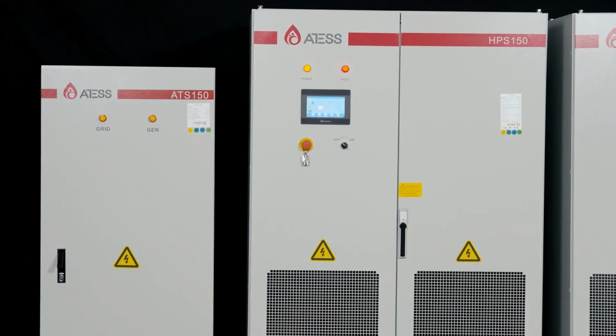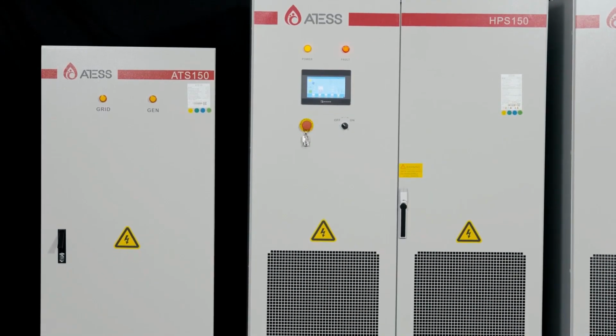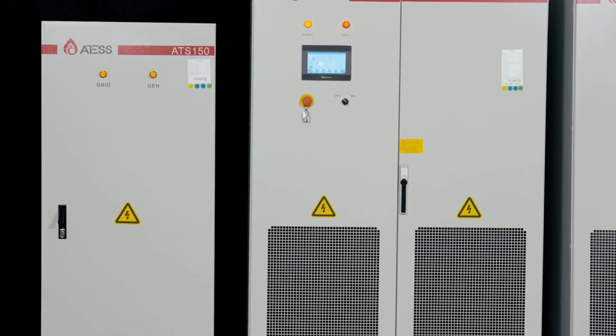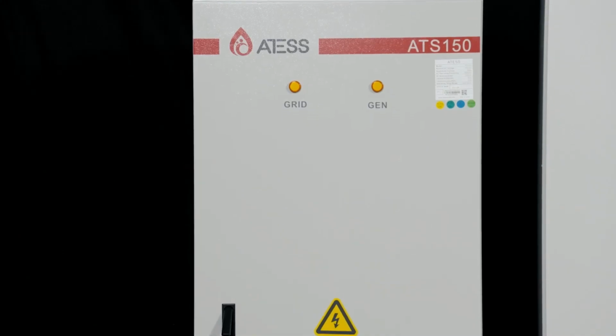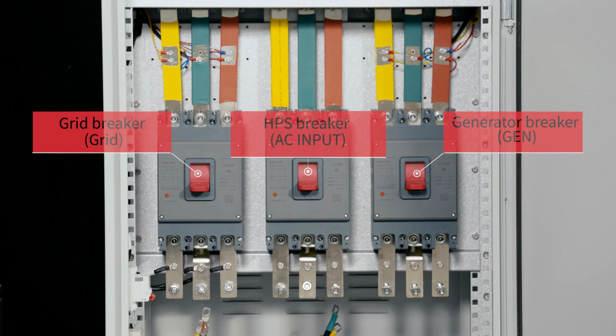When the system needs to be connected to the grid and the generator simultaneously, ATS is required. The function of ATS is switching between grid and generator. ATS has 3 breakers: grid breaker, HPS breaker, and generator breaker. Before connecting cables, ensure that the 3 breakers are disconnected.